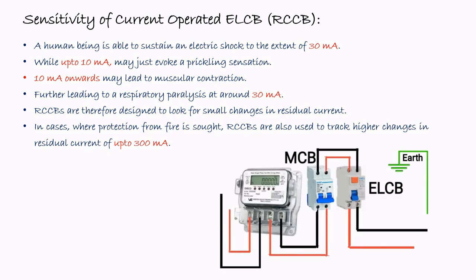So this is a circuit diagram, as shown, in a general circuit breaker. The power line is coming from the external supply. It will go through the energy meter. Then it will pass to the MCB, that is the main miniature circuit breaker of the building, and then it will pass through the ELCB. So generally, RCCB is more preferred than the voltage operated ELCB. Therefore, this ELCB can be considered as the RCCB or the current operated ELCB. And then the supply passes to the equipment.